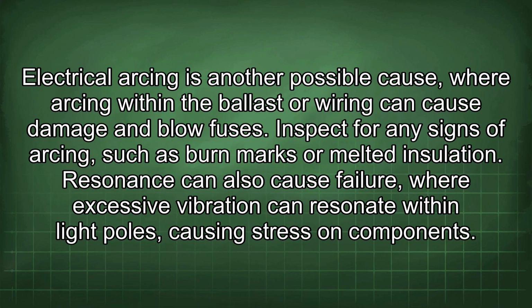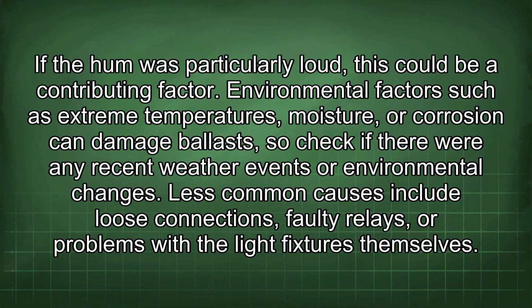Electrical arcing is another possible cause, where arcing within the ballast or wiring can cause damage and blow fuses. Inspect for any signs of arcing, such as burn marks or melted insulation. Resonance can also cause failure, where excessive vibration can resonate within light poles, causing stress on components. If the hum was particularly loud, this could be a contributing factor.